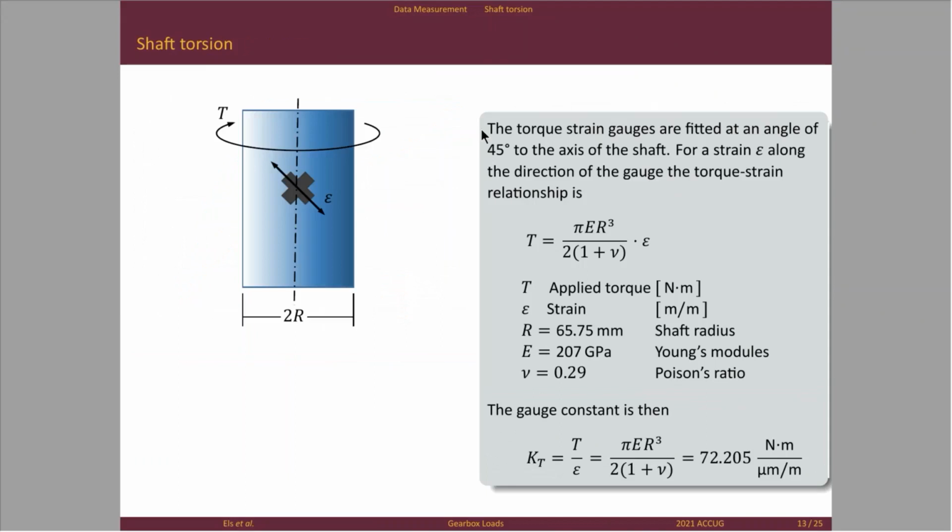So the next major measurement that we did was the torsion on the shaft. It was with strain gauges. You can calibrate the strain gauge simply from strength of materials. The unknown one here is Young's modulus, and Daniel Verbeek from Hansen has given us some values on Young's modulus, and that is for the highest quality of steel. It's still all over the show.